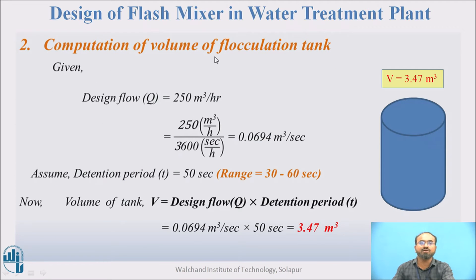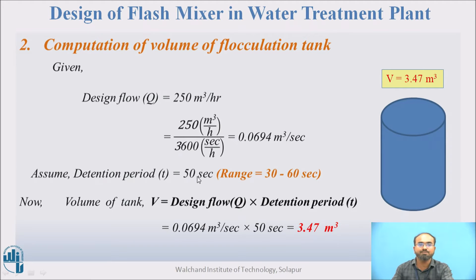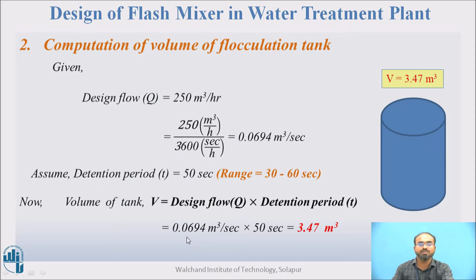For computation of volume of the flash mixer: the design flow Q is 250 meter cube per hour, which we convert to 0.0694 meter cube per second by dividing by 3600. The detention period is kept between 30 to 60 seconds; here we take 50 seconds. Volume V equals Q multiplied by T, so V equals 0.0694 multiplied by 50, giving a volume of approximately 3.47 meter cube.